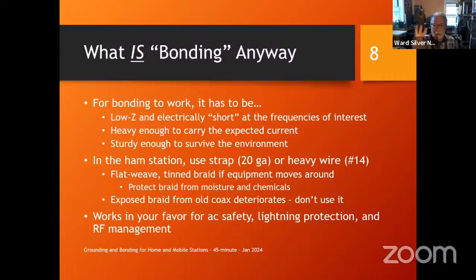So you've got 3 strikes against you: loose connections, corrosion, and water. All of those things are bad. So leave it in the jacket. Just treat it as a BAW, big ass wire. Put some pigtails on each end, put a terminal on each end, waterproof it, and you've got a perfectly good ground conductor. But the minute you take it out of that jacket, which is there to protect and compress it, it starts to degrade right away.